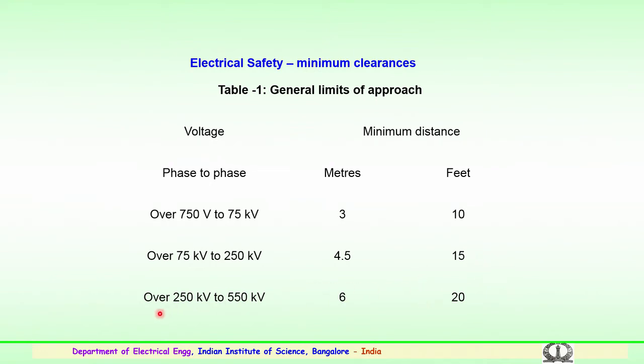Similarly, for 250 kilovolts to 550 kilovolts, a minimum distance of 6 meters or 20 feet has to be maintained. Further, if it is more than 765 kV or 800 kV, a minimum clearance of 9 meters, or approximately 27 feet, has to be maintained in the case of voltage levels of 765 or 800 kV. These are the standard values which are given in the manuals or safety standards.